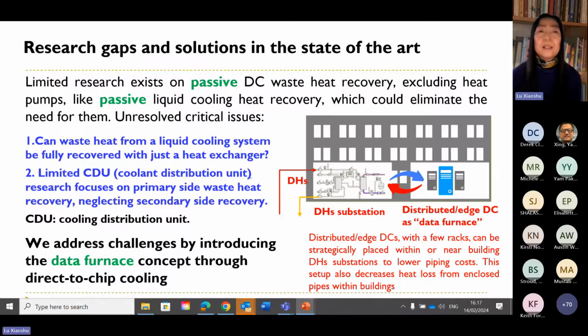Okay, two critical research issues can be summarized. First, can waste heat from a liquid cooling system be fully recovered with just a heat exchanger, without a heat pump? Second, limited CDU research has focused on primary side waste heat recovery only. Secondary side recovery has been completely neglected. CDU here represents coolant distribution unit or cooling distribution unit that distributes water or coolant in the liquid cooling system.